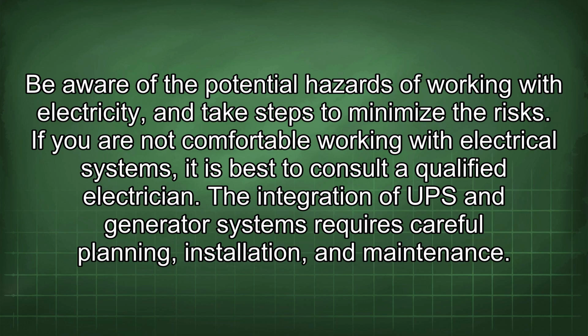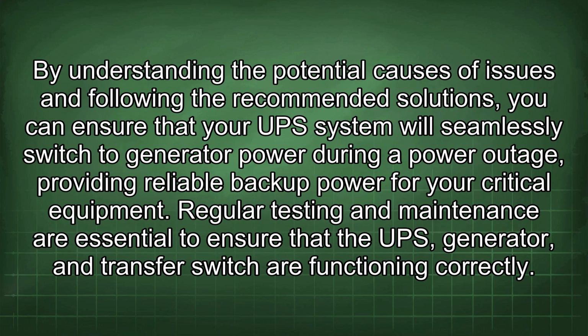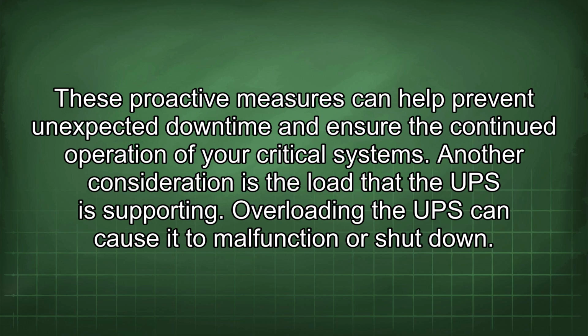The integration of UPS and generator systems requires careful planning, installation, and maintenance. By understanding the potential causes of issues and following the recommended solutions, you can ensure that your UPS system will seamlessly switch to generator power during a power outage, providing reliable backup power for your critical equipment. Regular testing and maintenance are essential to ensure that the UPS, generator, and transfer switch are functioning correctly. These proactive measures can help prevent unexpected downtime and ensure the continued operation of your critical systems.